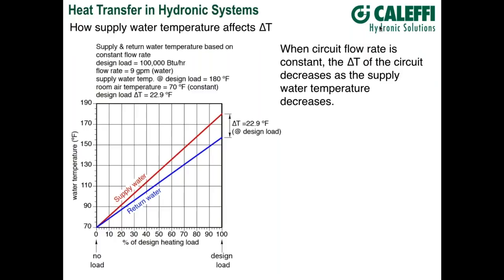How does supply water temperature affect delta T? Let's say we're changing supply water temperature based on heating load. At design condition — 100% heat output — we have a supply water temperature of 180°F. As we go to smaller percentages of design load, like half load, our supply water temperature can go down. This assumes constant flow rate and not varying the flow rate. Obviously, if we only need half as much heat transfer, we can do it with half the delta T we had under design conditions.